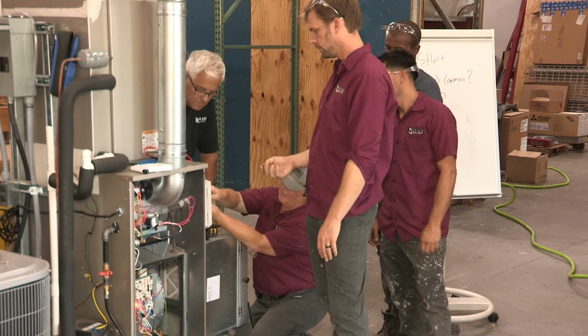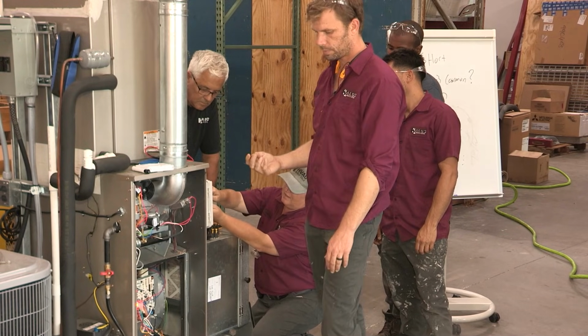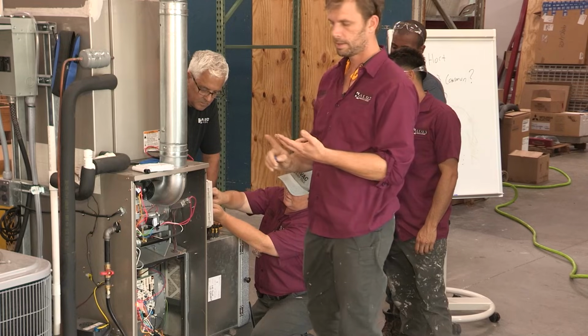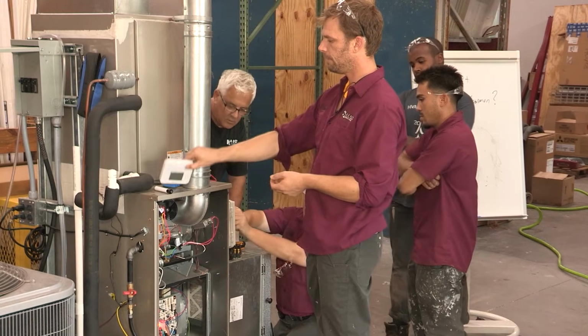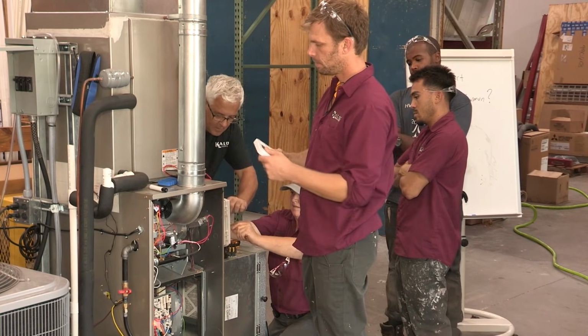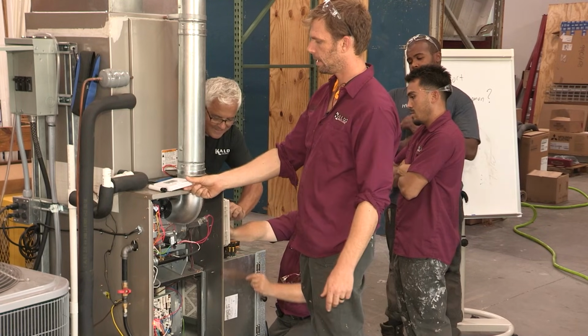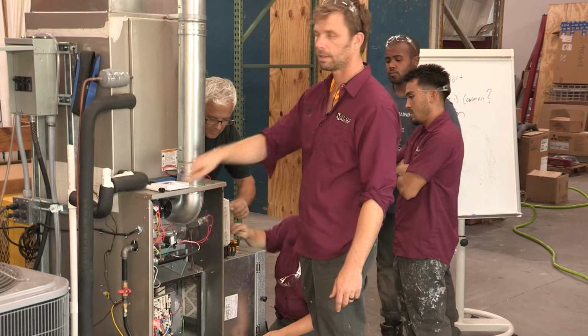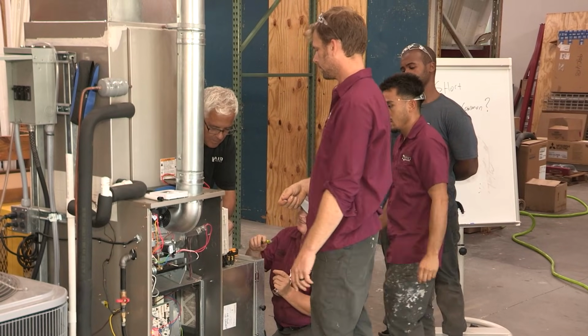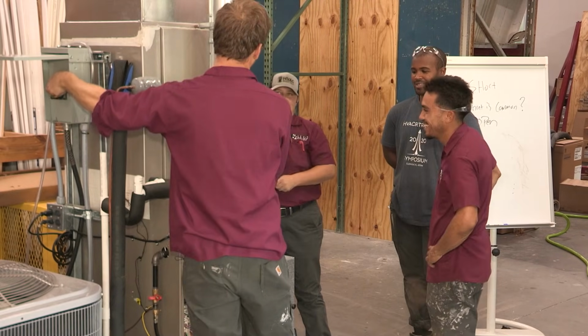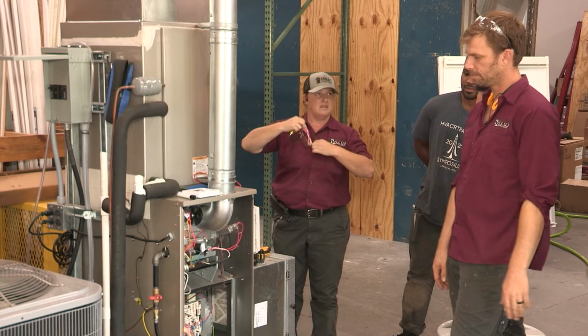Constant power. So then we're going to take a wire nut and we're going to jumper red, green, and yellow, and hopefully figure out why our time delay is resetting. Every time it expires, goes across 5 minutes, it resets. So we're going to try to figure this out. You picked up on something, you could hear it.